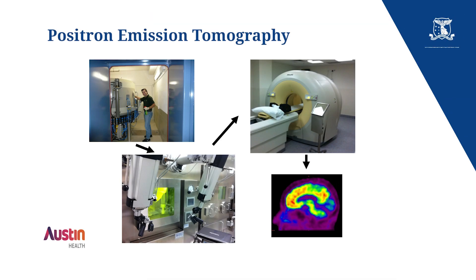PET starts with a cyclotron, which is a particle accelerator. You drop protons into it and by alternating magnetic and electrical fields, it accelerates these to a speed that's close to the speed of light and they slam into a target material, making the nucleus unstable and it becomes a positron emitter. The positron emitting compound is then transferred into a hot cell and it's labelled to a chemical that tags to the particular aspect of the patient that you want to image.